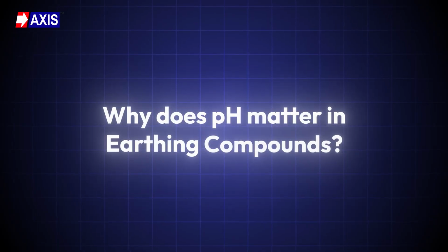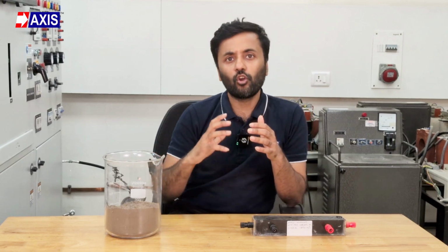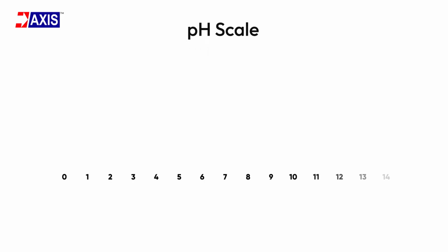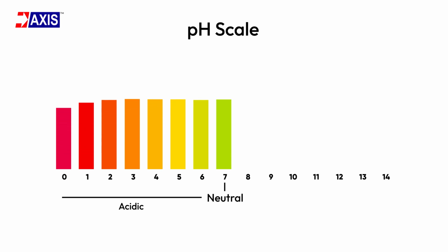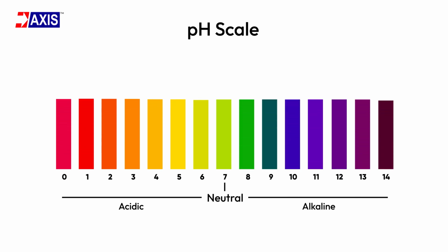Why does pH matter in earthing compounds? The term pH stands for potential of hydrogen. In simple words, it tells you whether something is acidic, neutral, or alkaline, and the scale goes from 0 to 14, where 7 is neutral, below 7 means acidic, and above 7 means alkaline. So for an earth-enhancing compound, the safest range is close to neutral.